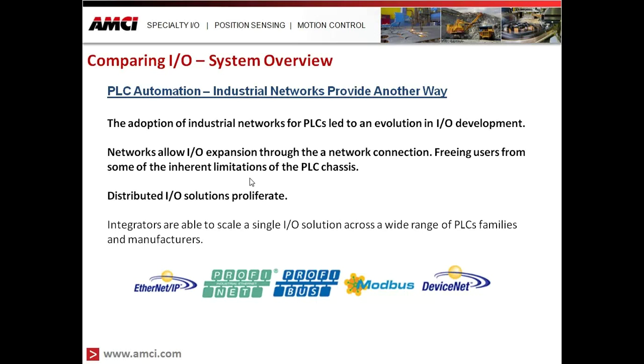Integrators are now able to scale a single IO solution across a wide range of PLC families. You could pick a distributed IO solution — the type of inputs, outputs, and specialty solutions you wanted — from one supplier and use that with different manufacturers' PLCs. Whether it was a PLC or PAC, you could standardize on one particular IO. These systems are available across a wide range of industrial networks, including EtherNet/IP, PROFINET, PROFIBUS, Modbus TCP, Modbus RTU, and DeviceNet.